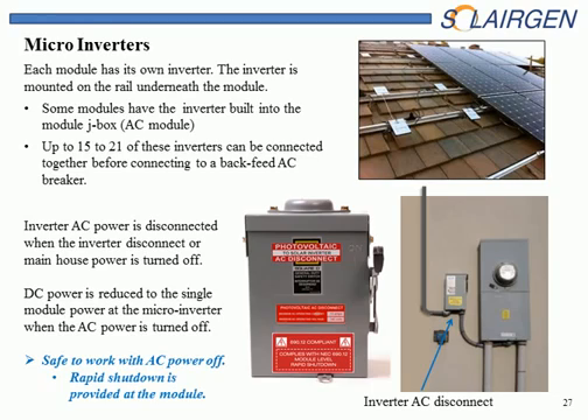If you want to shut the power down, there's two ways to do it. You can pull the meter, or you can disconnect the main inverter AC disconnect, which is shown here in this picture. It states that it's a photovoltaic AC disconnect that's required by the NEC and by the utility. It'll also state what the operating voltage is and the operating amperage. And it may state down below that it complies with the 2014 rapid shutdown requirement. Now that may or may not be there on a microinverter.